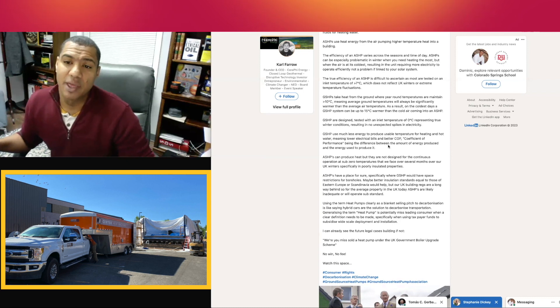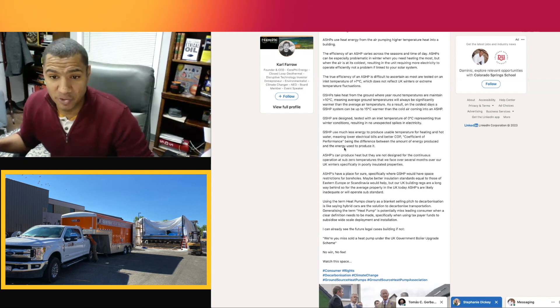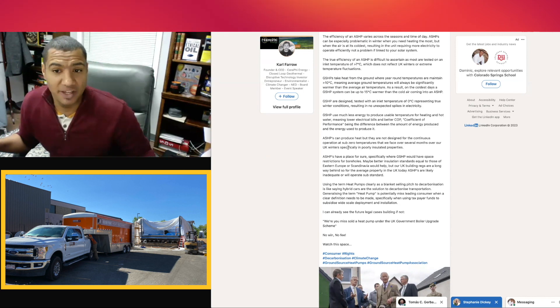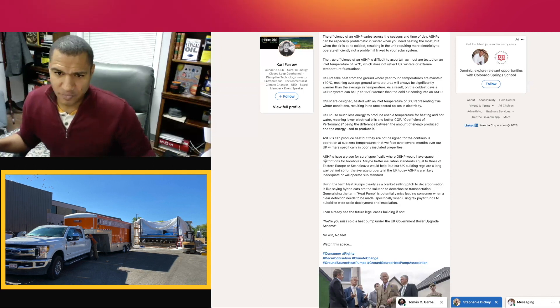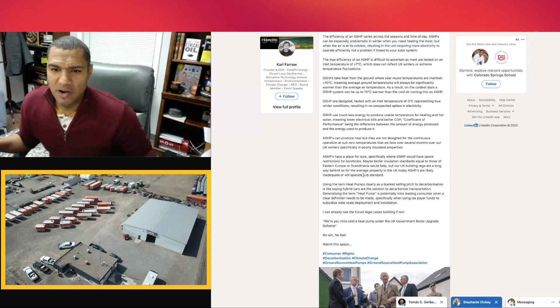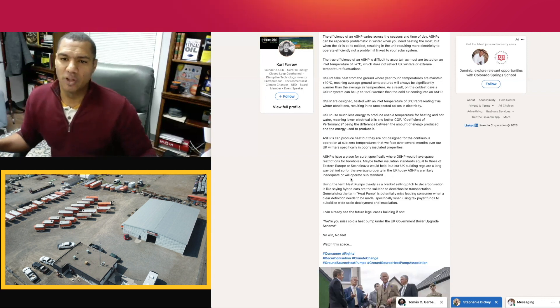'Ground source heat pumps use much less energy to produce usable temperature for heating and hot water, meaning lower electric bills and better COP — coefficient of performance — being the difference between the amount of energy produced and the energy used to produce it. Air source heat pumps are not designed for continuous operation at sub-zero temperatures over several months of a UK winter, specifically for poorly insulated properties. Air source heat pumps have a place — specifically where ground source heat pumps face space restrictions for boreholes.